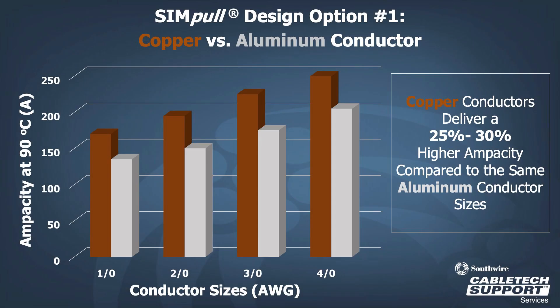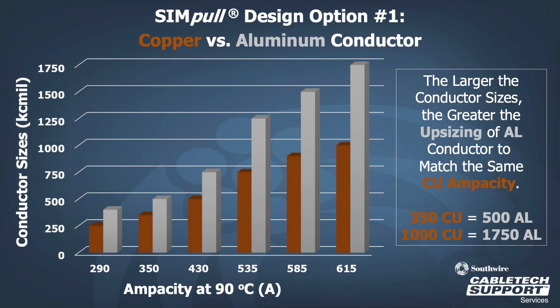For an aluminum conductor to carry the same ampacity as a copper conductor, the aluminum conductor would need to be upsized. Copper conductors deliver 25 to 30% higher ampacity compared to the same size aluminum conductors, depending on the size of the conductor. In this graph we can see that larger conductor sizes require upsizing aluminum conductors to match the same copper ampacity. A 350 kcmil copper conductor and a 500 kcmil aluminum conductor have equal ampacities — essentially, the aluminum conductor is two sizes larger than the copper conductor.